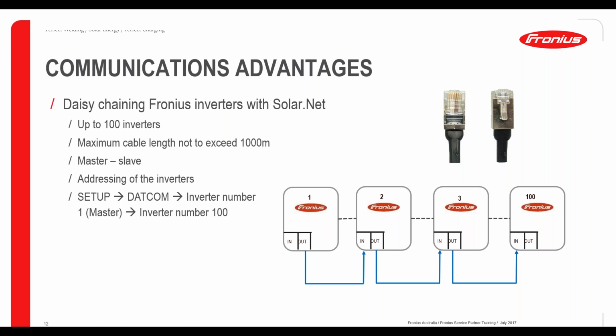An important thing to realize is this is what's called a multi-drop configuration, which means there will be one master and all the rest of the inverters will technically be called slaves. The master will drive the communication in the back end. With a master-slave combination, it's also important to dedicate inverter IDs or numbers starting from 1 to typically 100. You have to be careful when commissioning that you don't have the same IDs, because this will cause that specific inverter to lose communication.